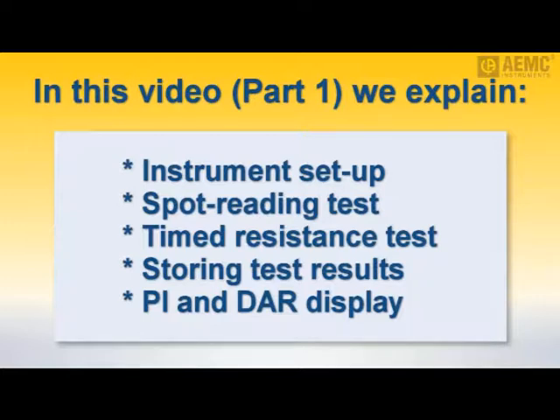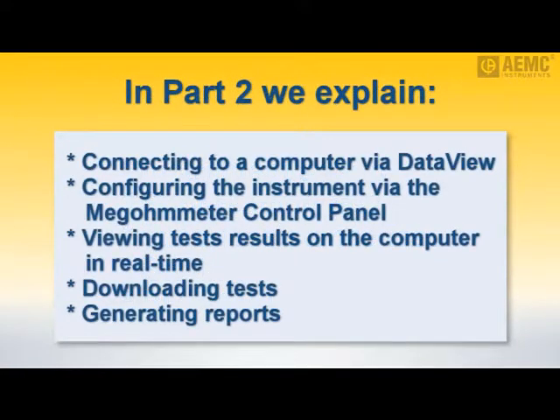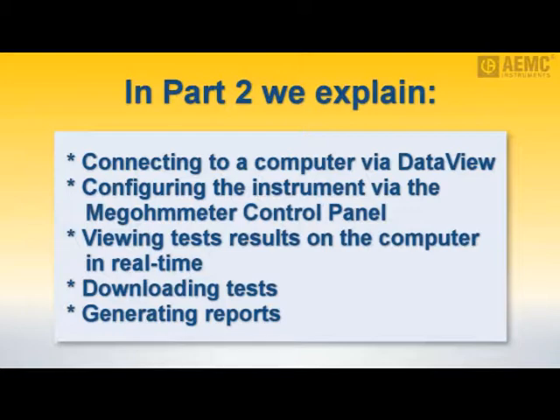We also show how to display polarization index and dielectric absorption ratio values, both of which are automatically calculated by the instrument. In Part 2 of this series, we discuss using the Model 1060 with DataView, AEMC's data analysis software. This will include instructions for connecting your computer to the 1060, configuring the instrument from the DataView Megohmmeter Control Panel, running a test and viewing results in real time, downloading tests stored on the instrument, and generating reports from this data.